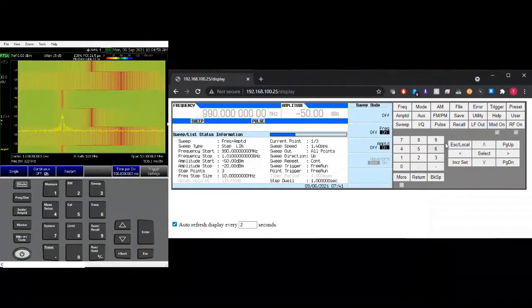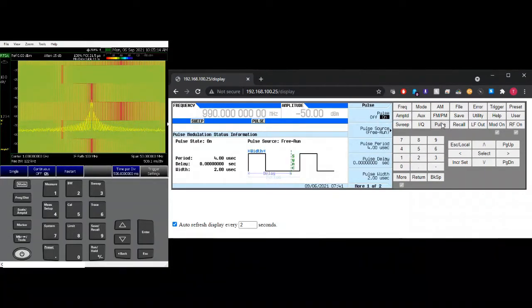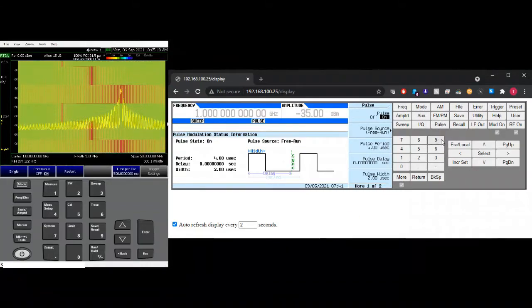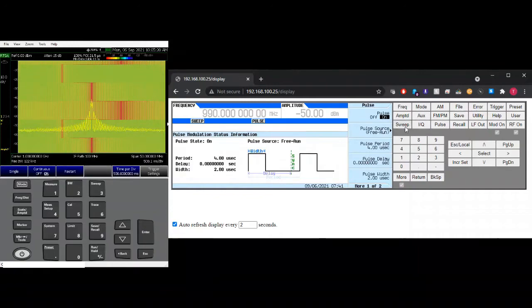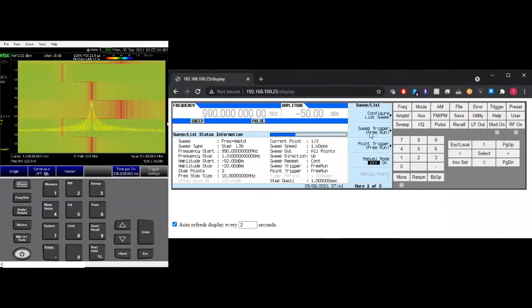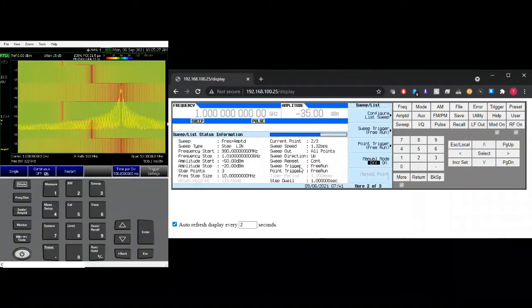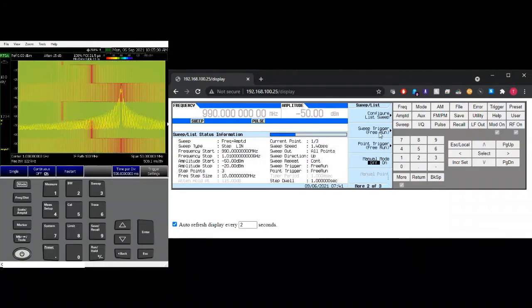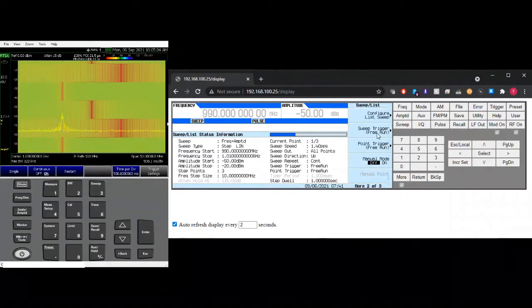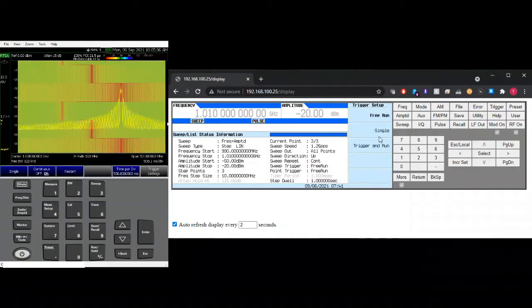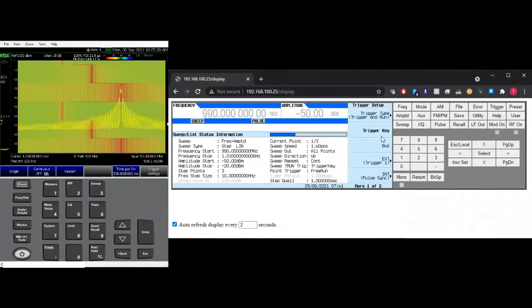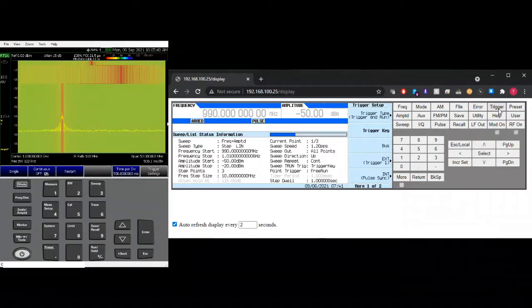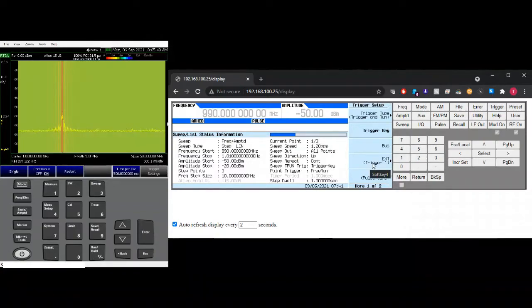So how about if we turn off the pulse, if you need a trigger in to start the pulse. So we can do it here. Just go to sweep mode. So because right now this sweep step is set to free run. So instead of free run, we set trigger and run. So this trigger key is here on the ESG. So manually you can do that. Or you can use the external trigger one as the input.